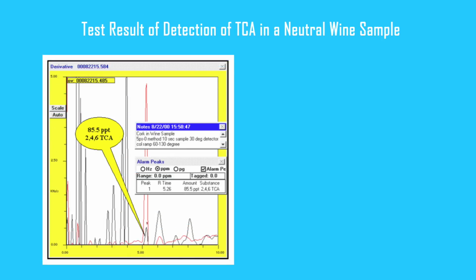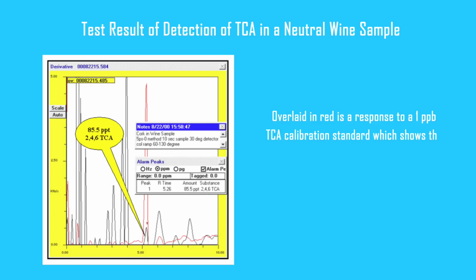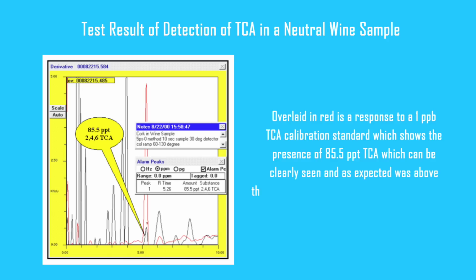Test results of detection of TCA in a neutral wine sample, overlaid in red, show a response to a 1 ppb TCA calibration standard, revealing the presence of 85.5 ppt TCA, which can be clearly seen, and as expected, was above the odor threshold of 5 to 10 ppt identified by the expert panel.